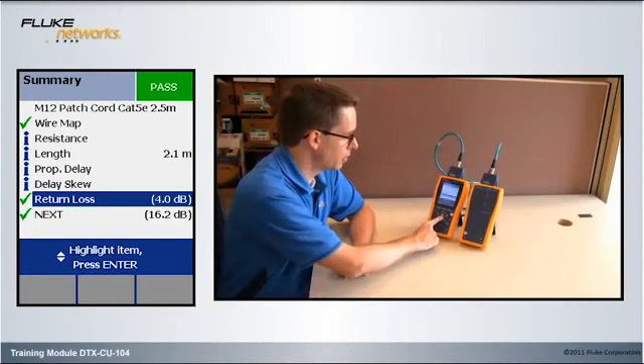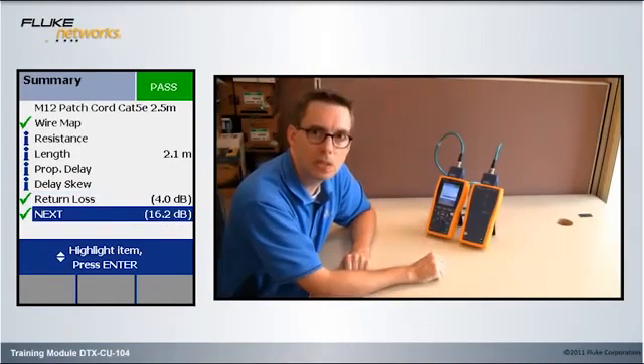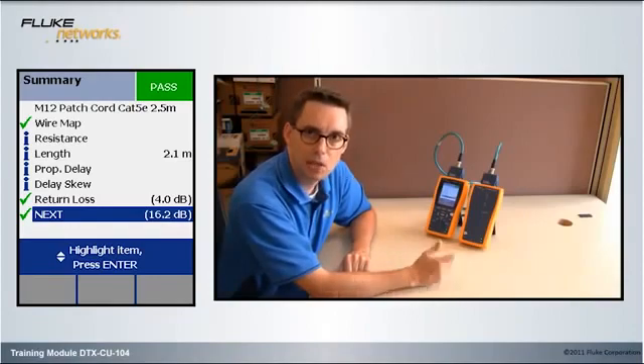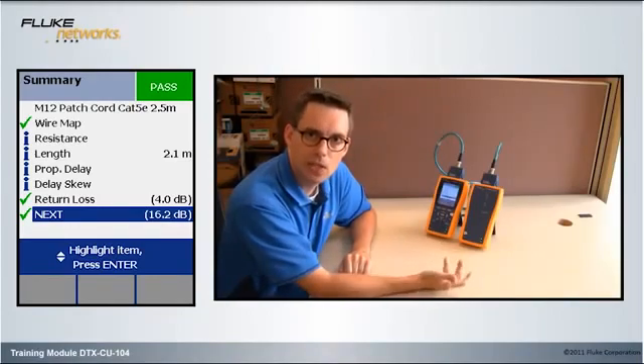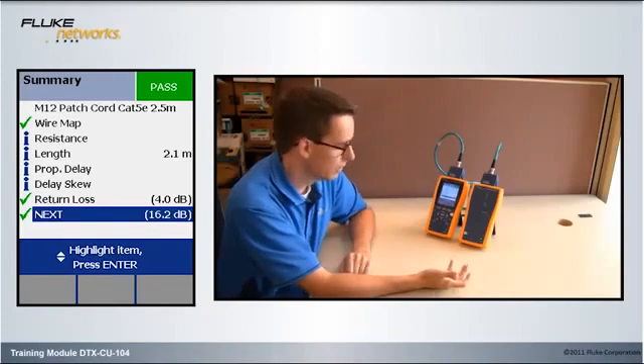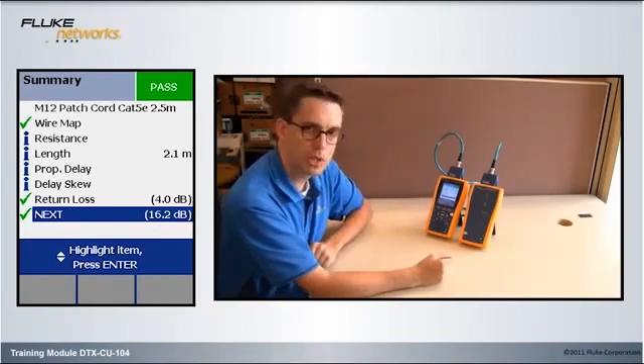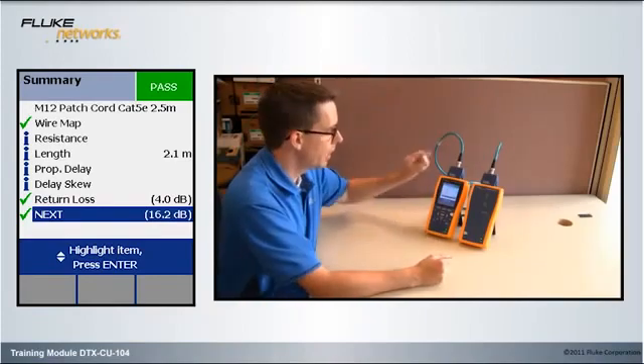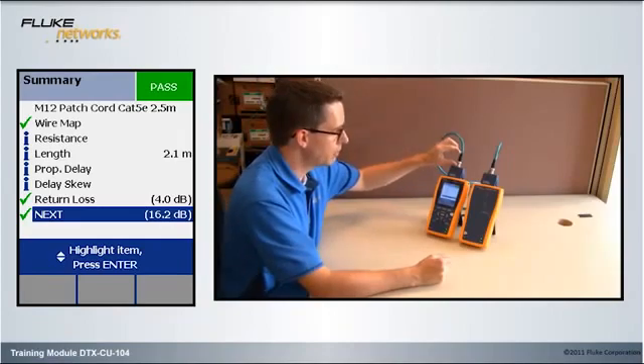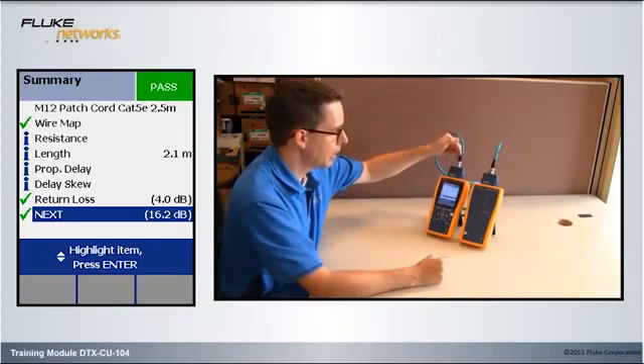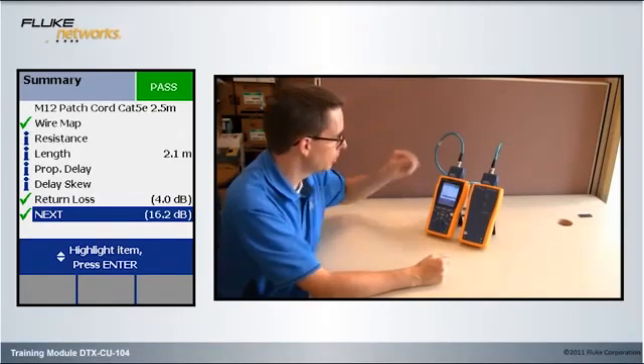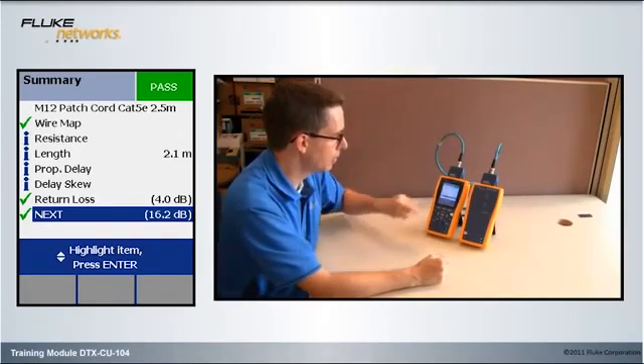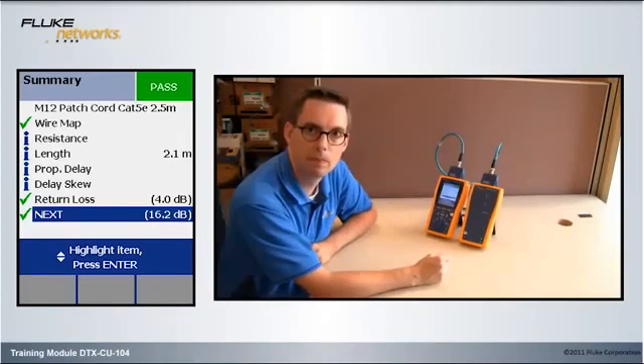And then we see near-end crosstalk showing 16.2 dB. Is that a good figure or a bad figure? Well, 6 dB is a factor of two. So, this is a really nice patch cord. Whoever did the termination of this M12 here and here, clearly maintained the twist going into the back extremely well. Coupled with a very nice performing cable gives us excellent margin.